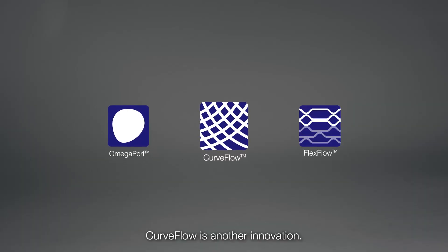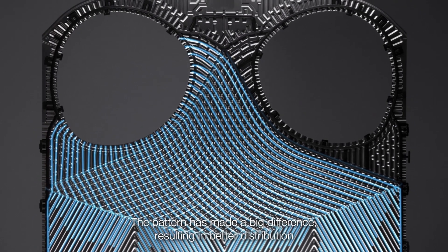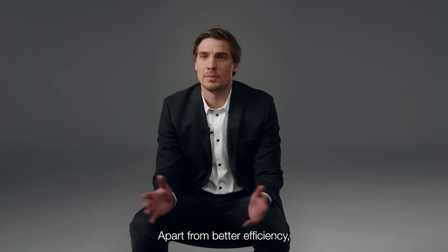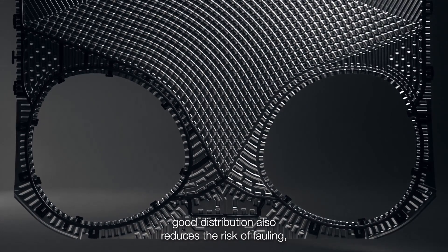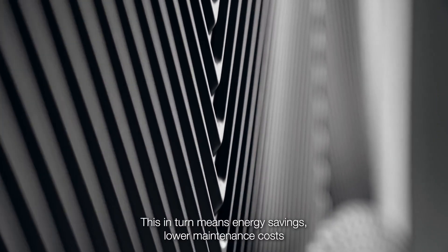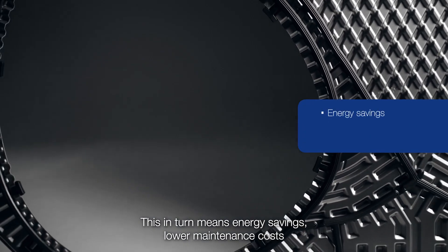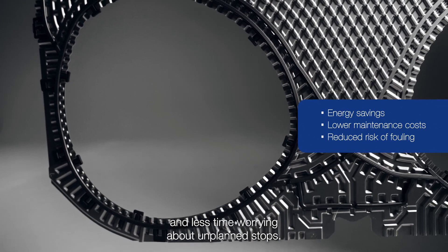CurveFlow is another innovation. The pattern has made a big difference, resulting in better distribution and lower pressure drop. Apart from better efficiency, good distribution also reduces the risk of fouling, which means you can run the heat exchanger longer between cleanings. This in turn means energy savings, lower maintenance cost, and less time worrying about unplanned stops.